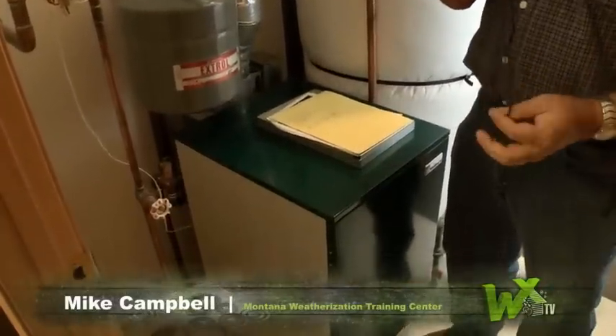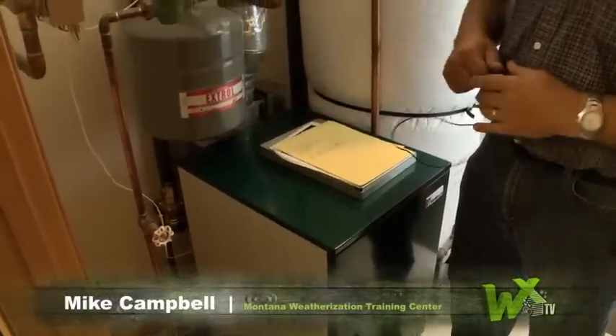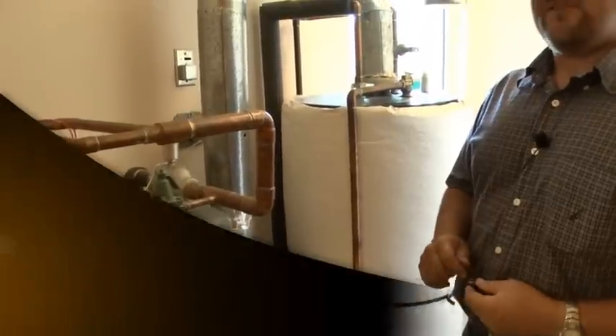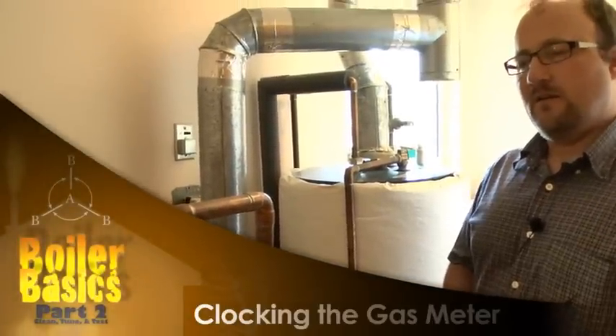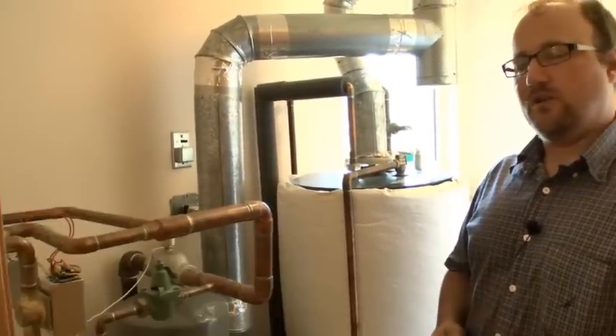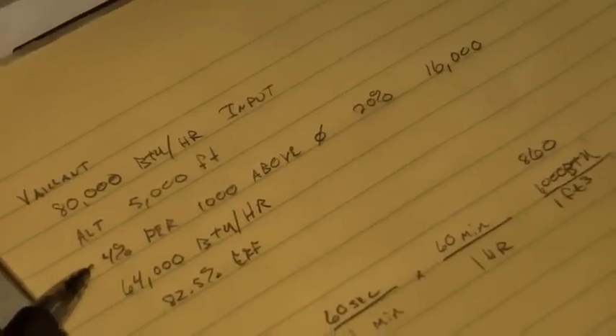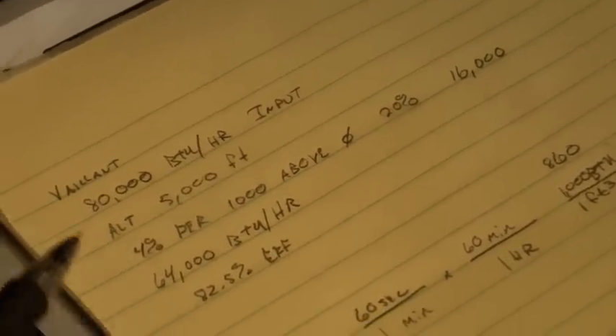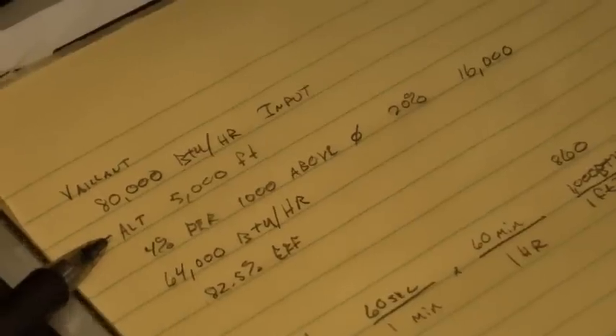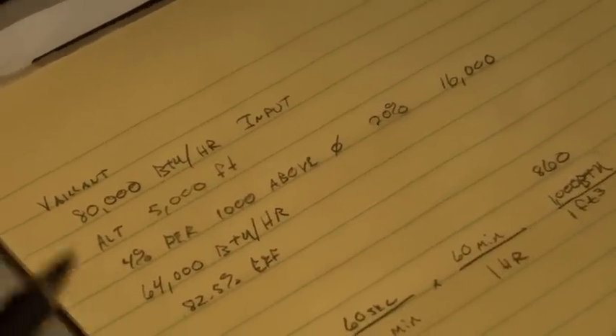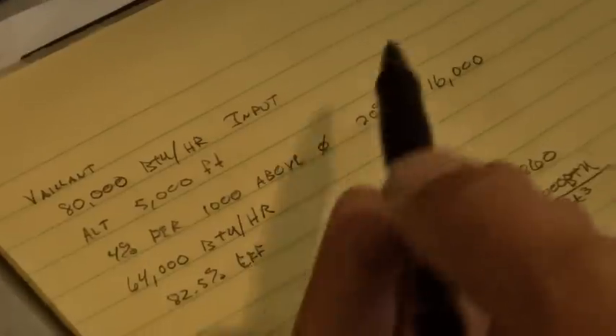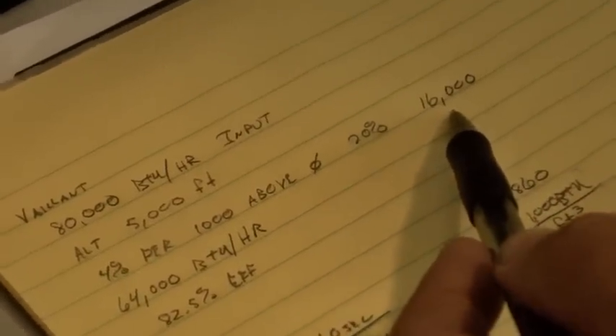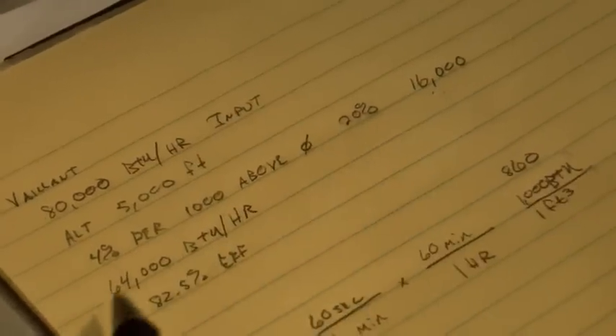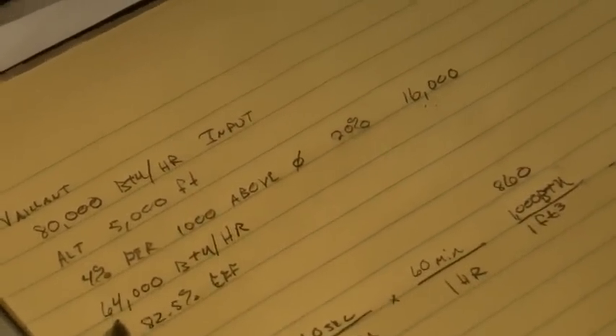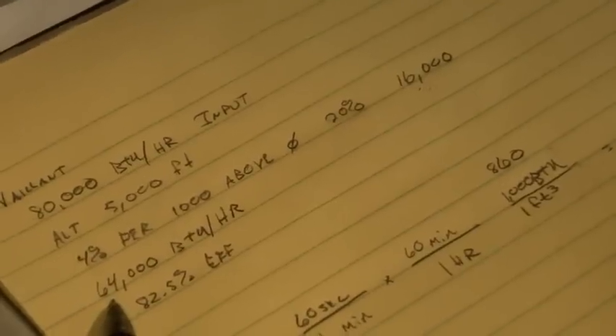The way we're going to do that, since this is a natural gas system, is we're going to clock the gas meter. We're at an elevation of 5,000 feet here, so we have to derate the input into this boiler 4% for every 1,000 feet we are above sea level. We're at 5,000 feet above sea level, so we have to derate this boiler by 20%. This is an 80,000 BTU boiler. At 5,000 feet elevation, we should be seeing 64,000 BTUs of fuel being supplied to this appliance.